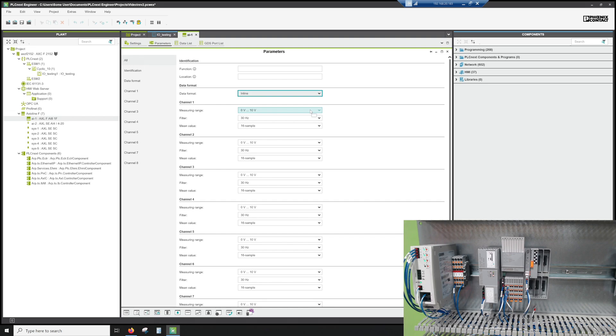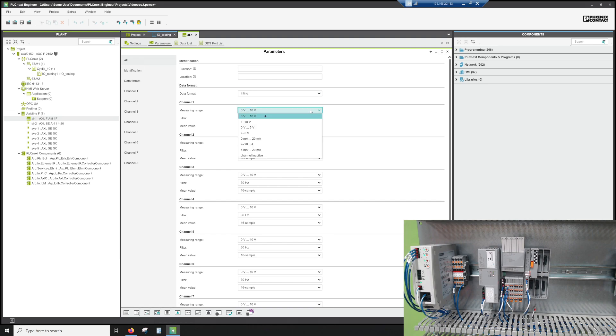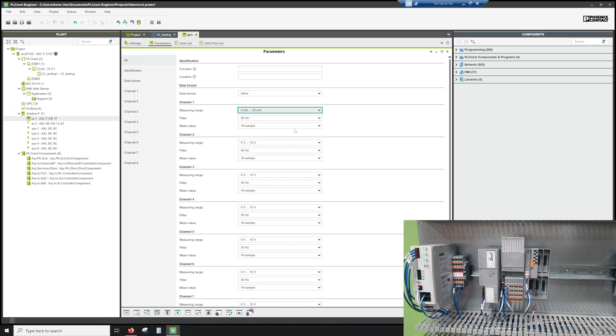Looking at the wiring, on the left-hand side channel one is wired for current because the bottom two terminals are current input and the upper two terminals are voltage input. We're going to do a 4 to 20 milliamp on channel one and zero to 10 volts on channel two.